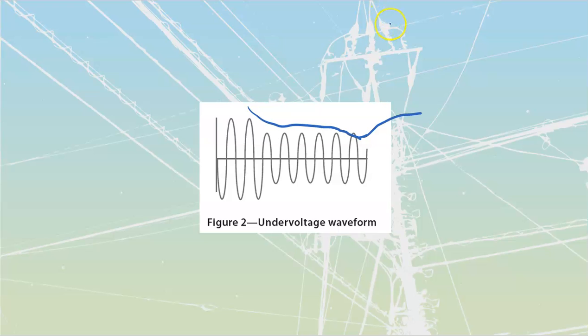If I do have under voltage, it's going to usually cause equipment to shut down. A lot of critical equipment has under voltage protection, which detects that the voltage is too low and shuts it down rather than letting it cook itself. The causes of under voltage usually come down to current through the system.